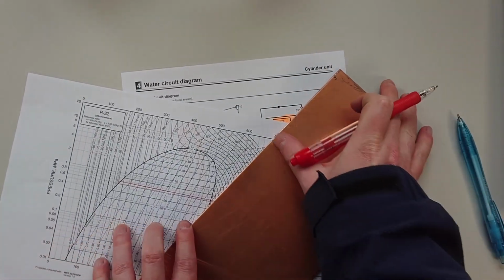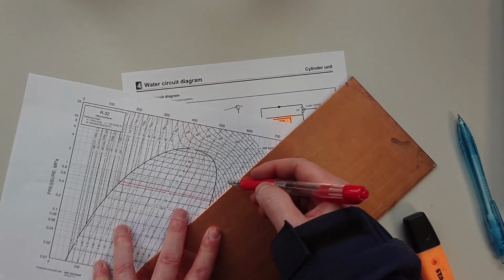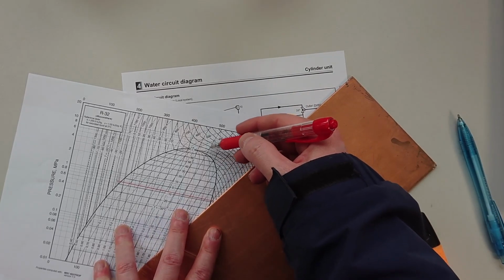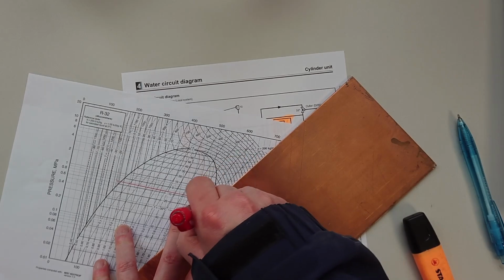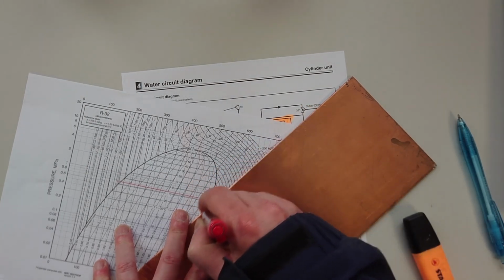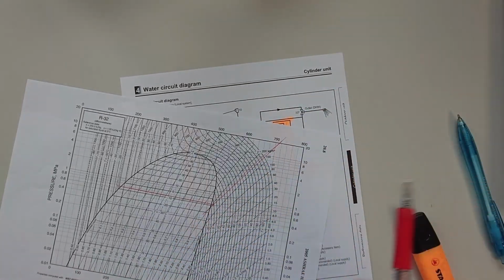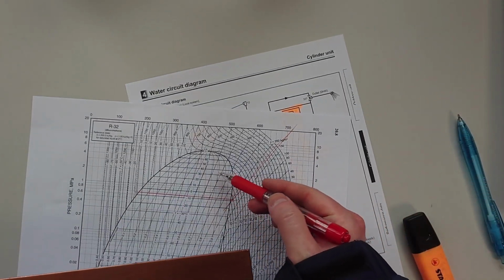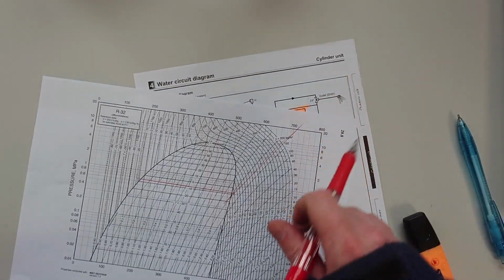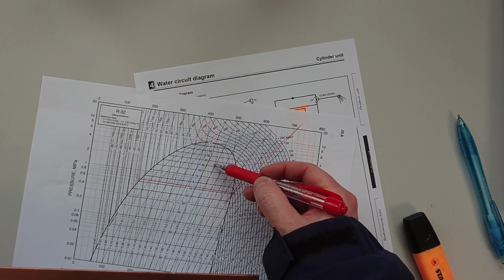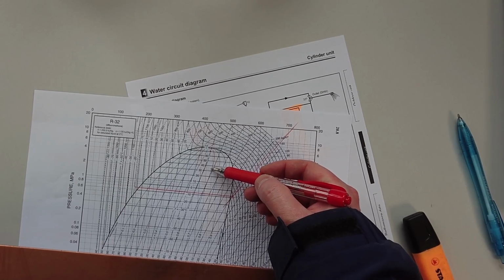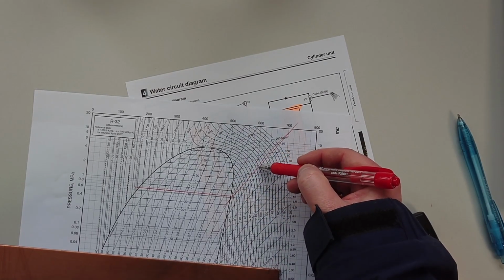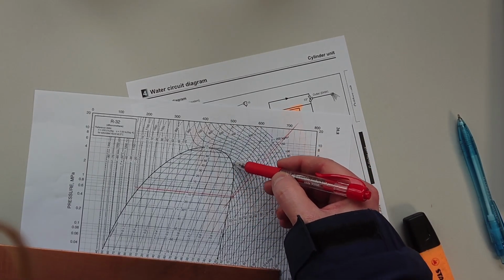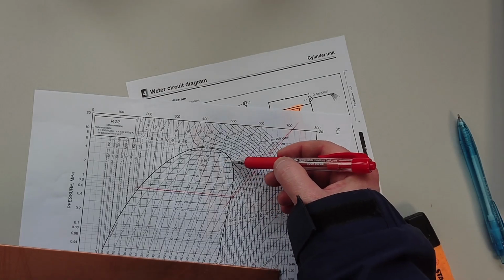And now what happens is that you have to compress it, which is where your energy comes from that you're putting in through your power measuring device, whatever it is in your house. And we're just going to draw a made up line up here somewhere. And then what happens is we'll have some temperature above, because we need 35 coming out, which is here. The refrigerant itself will be condensing higher than that because you need heat exchange. So we'll put it just arbitrarily around this 50 mark here.